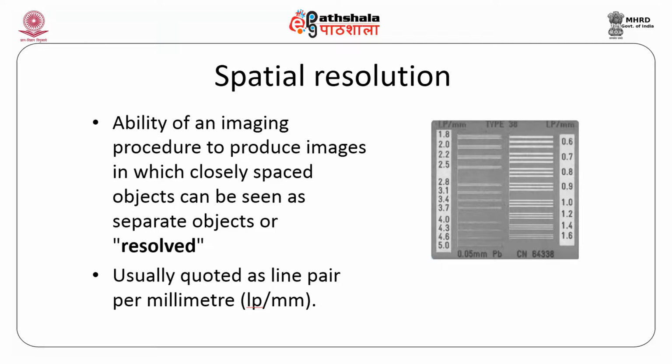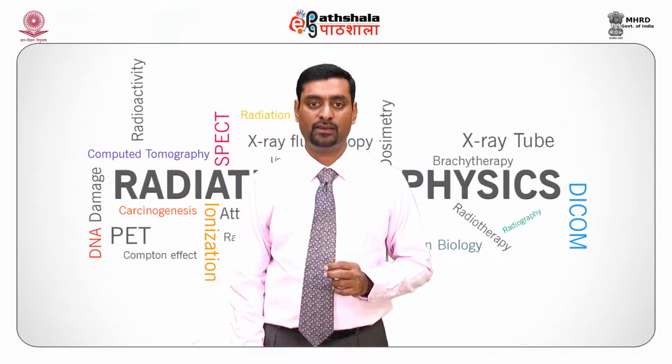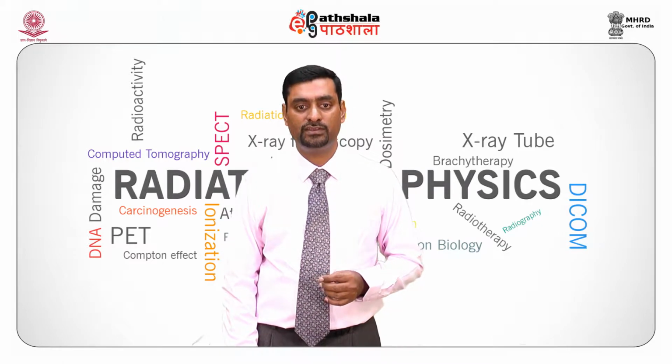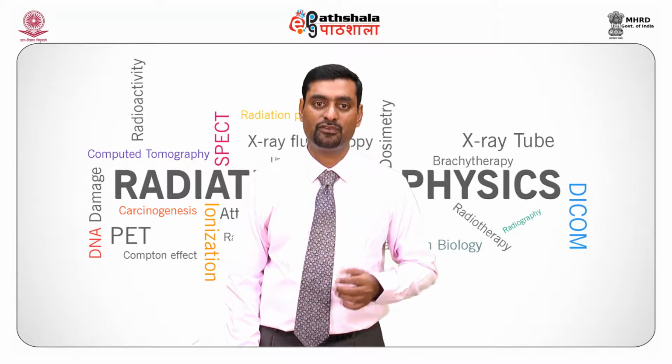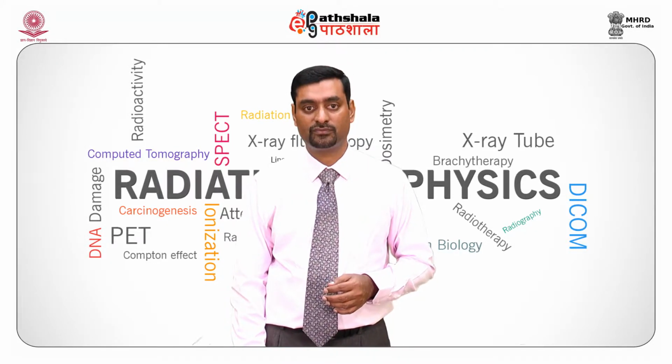Here we can also go till 2.5 or 2.8, where we see that these lines are seen distinctly, indicating that the detector which has taken this image is capable of visualizing images up to 2.8 line pairs per millimeter. Hence, it is quoted as line pairs per millimeter, and that is the description for spatial resolution.